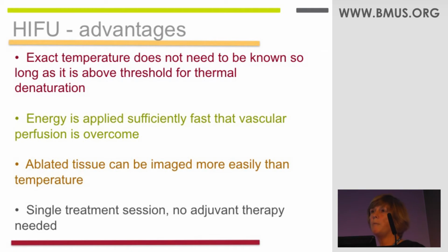Well, as long as you're above your 55 degrees, you don't need to know whether you're at 60 or 80. So the thermometry is not such a big problem, as long as you're above the threshold for thermal denaturation. When you do hyperthermia, blood supply is a problem because the blood supply carries the heat away. However, if you can give your high energy very rapidly, the thermal conductivity from the blood supply doesn't matter. You've already reached your temperature for protein denaturation before the heat is carried away. And we're talking about 1 second, 2 second exposures at very high intensities.